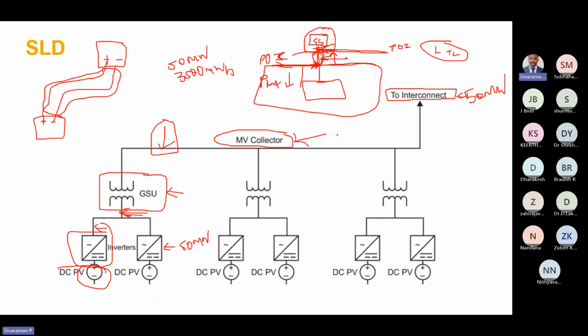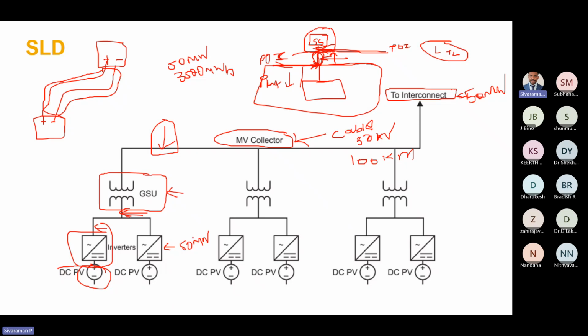So this is the collector network. Here the cables will be there. Let's say it is 33 kV cable, and let's assume the cable length is almost 100 kilometers. So totally we are going to have 100 kilometers of cable. The inverters are rated for 50 megawatt, but due to the losses in the AC cable, the inverter duty transformer and the AC cable, at the interconnection point we can't get 50 megawatt. It will be reduced to some other value. It will not be 50 megawatt.